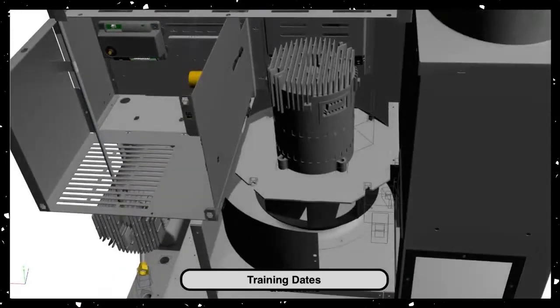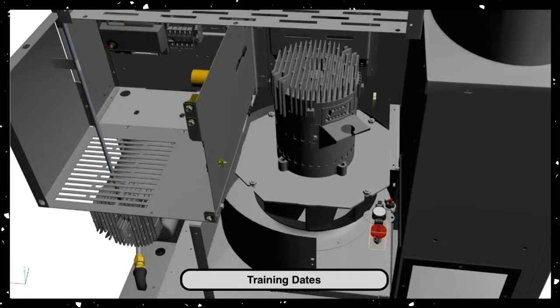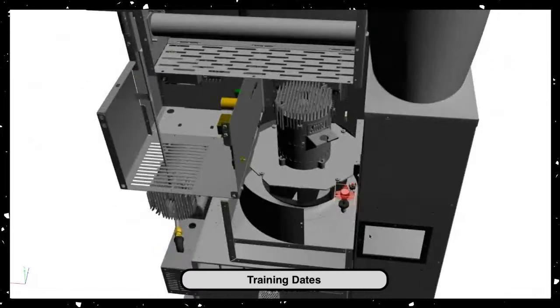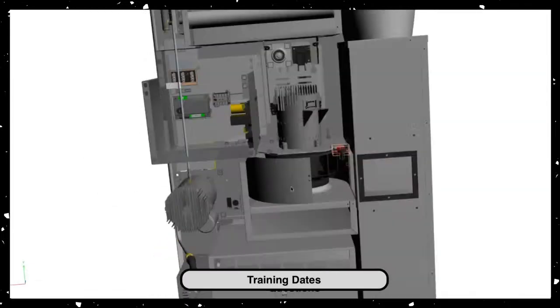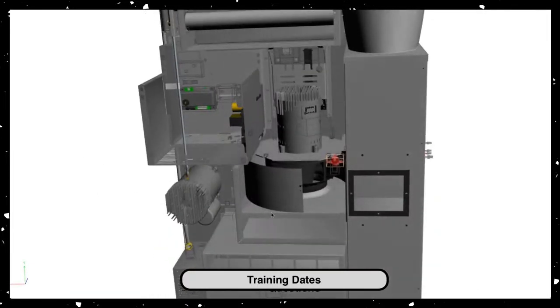If we look here as I tilt it, this is your thermistor that does your temperature reading. But here's an auto reset, and here's a manual reset—this is the cabinet limit thermostat. So strategically, these two are located next to the thermistor, so if we ever had a false reading on the thermistor for whatever reason, this would be our savior there. Again, easy to locate on the machine, and with this rendering it helps us quite a bit to do that.